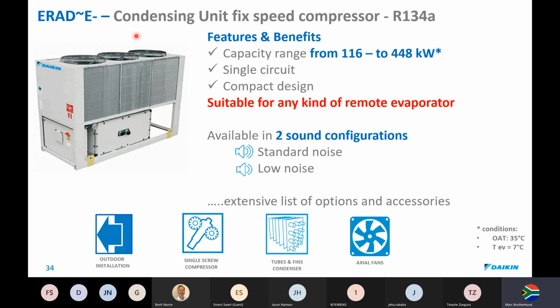So this is pretty much our entry level in screw compressors. It's condensing units with a fixed speed compressor, so this is non-inverter. Available in 2 sound levels and suitable for any kind of remote evaporator. So this chiller does not come with an evaporator. This is purely a condensing unit. It will have a compressor, your condensing fins, or your condenser, I should say, and your fans to help the condensation.